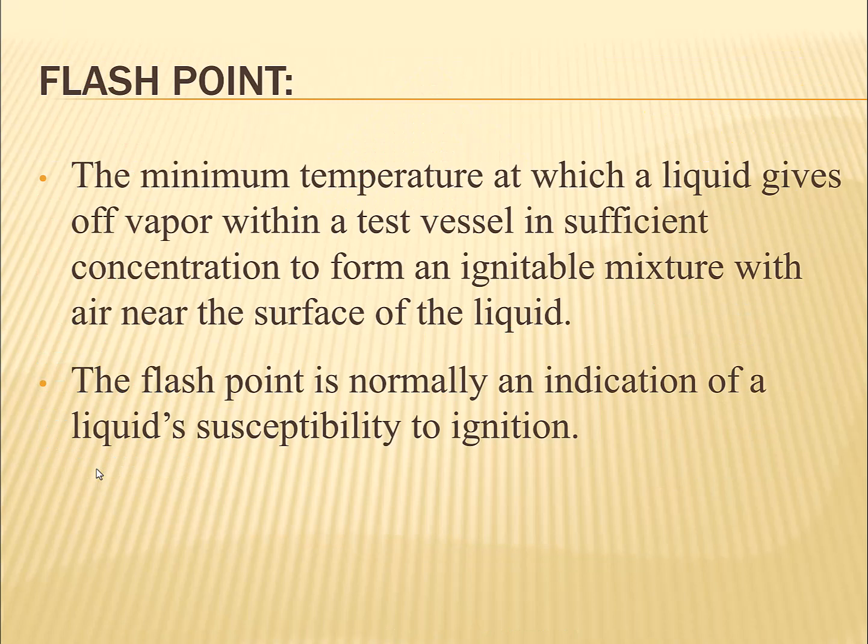So the flash point is the minimum temperature at which a liquid gives off enough vapor within a test vessel, if you want to get technical, in sufficient concentration to form an ignitable mixture with air near the surface of the liquid.